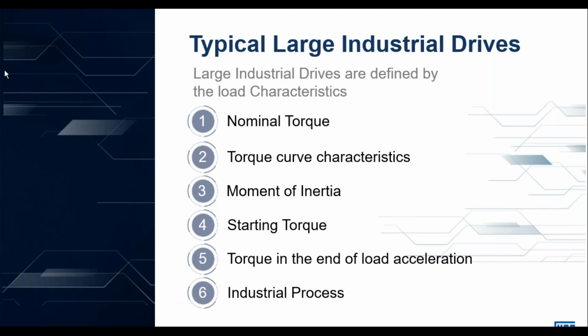These I've just divided up into categories. So we need to know the nominal torque. This would be the rated continuous torque that the motor is needed to produce to run the load in a steady state condition. Then we need to have the torque curve characteristic of the load and of the motor, and ensure that the motor is able to accelerate the load. And this is more of a dynamic analysis. Then we need the moment of inertia. This is useful in calculating the acceleration time and making sure that thermally the motor is able to accelerate the load without exceeding its thermal rating or capability.